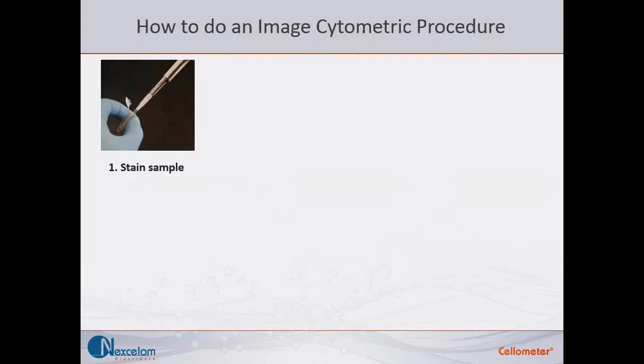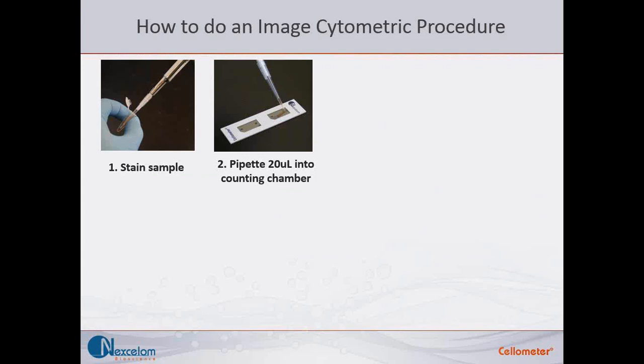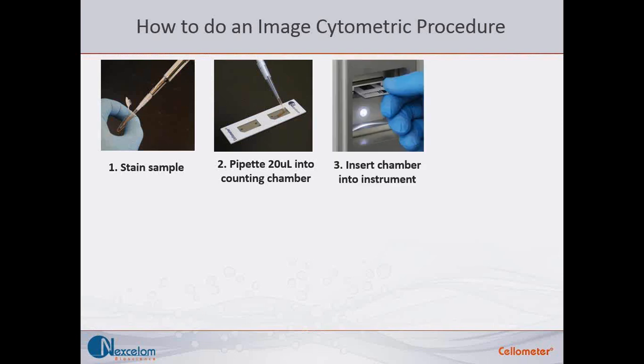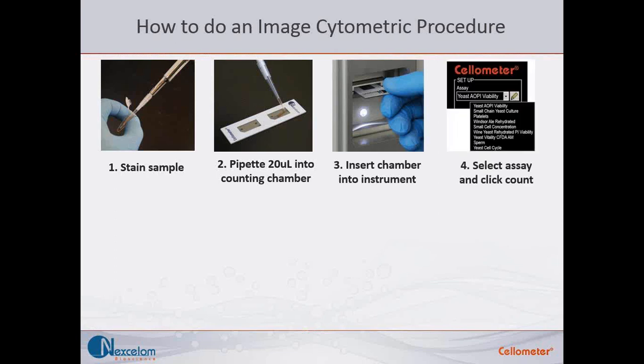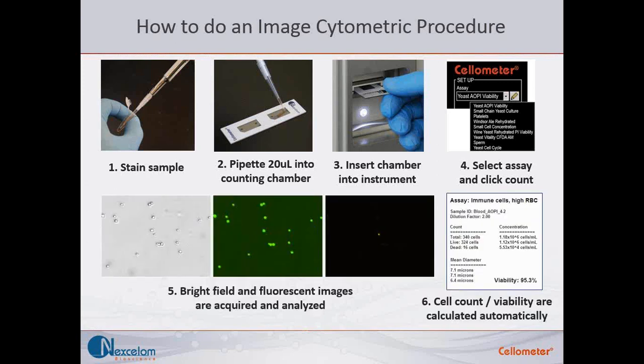The image cytometric procedure involves: first, collect the sample and stain with propidium iodide; then pipette 20 microliters into a counting chamber; insert the chamber into the system; select the specific assay for your sample. The system will then take several images for both bright field and fluorescence to analyze, and finally give you a cell count and viability automatically.